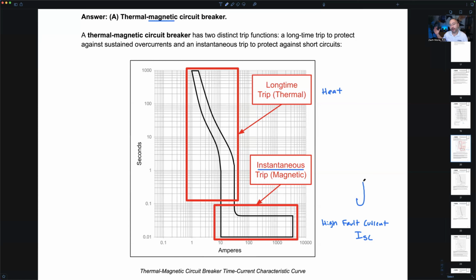And when I have a really high fault current, I also have what? Anyone familiar with Maxwell's equations? Not in the PE exam, but at least that relationship. More current equals more flux, or a bigger magnetic field, right? They're proportional. More current, more amps, more magnetic field. So as the current flows through the hook shape, the curve in the breaker, when the current is really big, the magnetic field around it is really big, and it ends up creating a magnetic field strength so strong that it opens the breaker contacts.